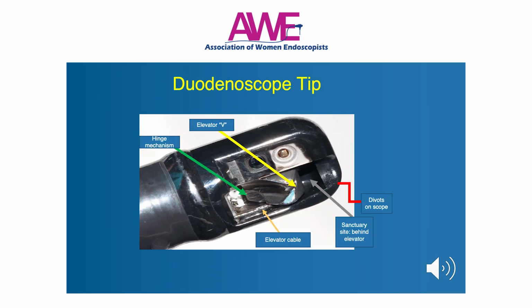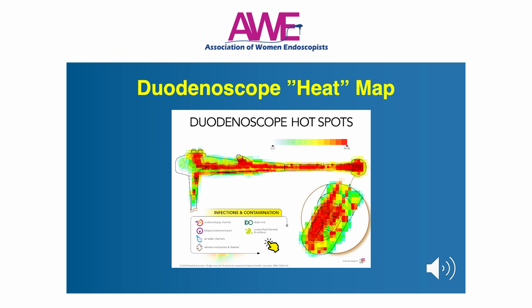We know that part of the problem is the duodenoscope tip, which is very complicated. It has this elevator with sort of a sanctuary behind the elevator, an elevator cable, sort of this elevator V-notch, hinge mechanism, divots on the scope, and these can all be sources of infection. A duodenoscope heat map here shows that there is evidence of not just the tip, but also it can occur in the channel. And so this is one of the challenges for the current trend towards disposable caps and elevators, in that while they may present some improvement, there may be residual risk in the channels.